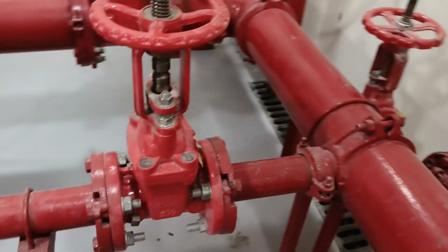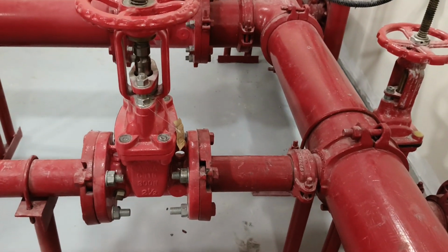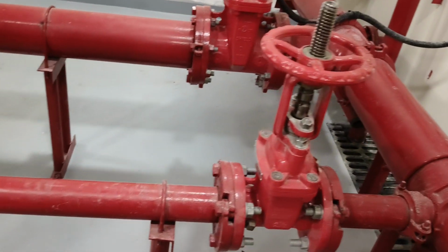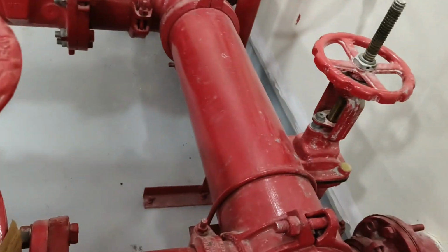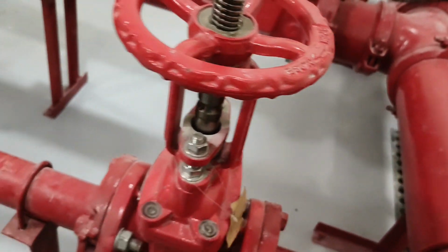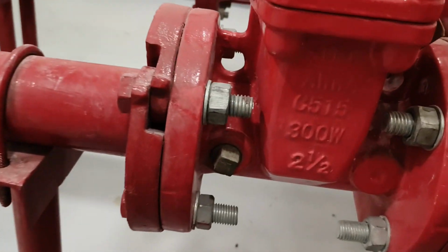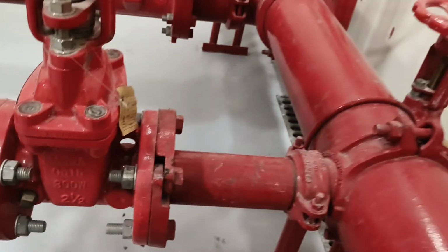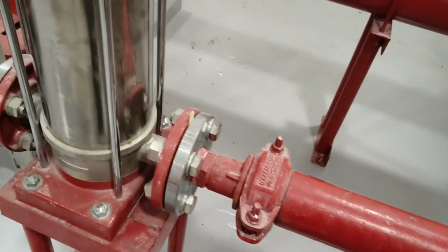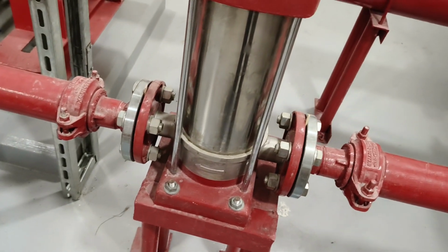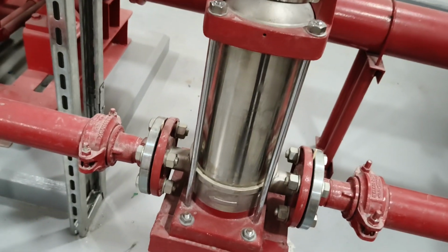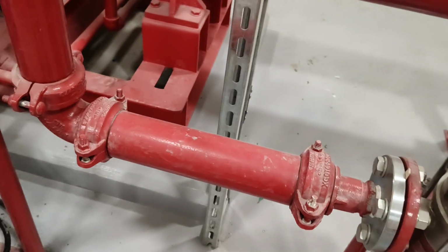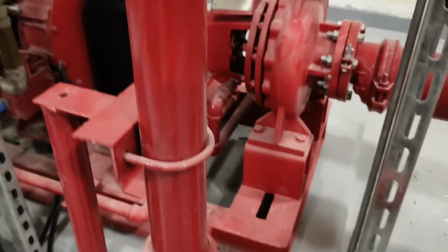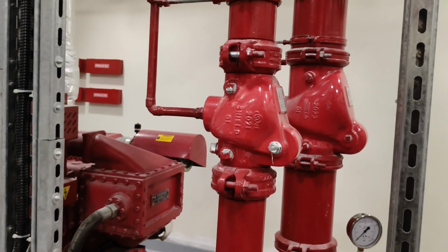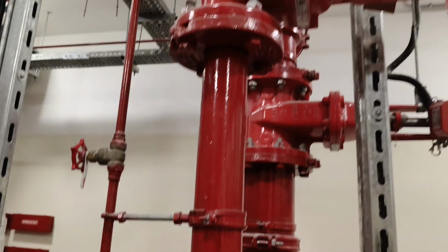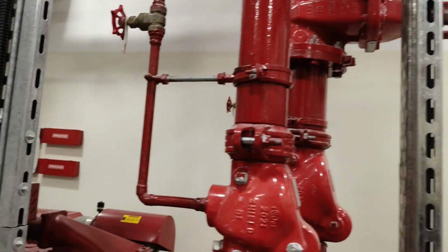So the jockey's own is being tapped here on a 2-inch with a 2-inch valve, okay? No, this is actually 2.5, all right? So it's 2.5, yes. Then here it's being reduced to the pump itself, then also another reducer to a 2.5 inch. Then we have this check valve. Between the check valve and the valve, we have the sensing line.